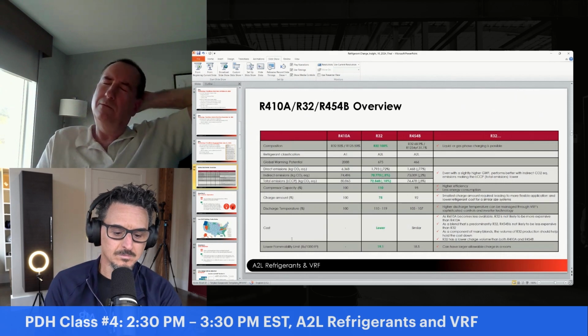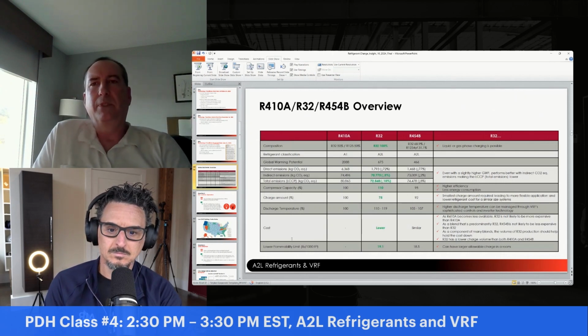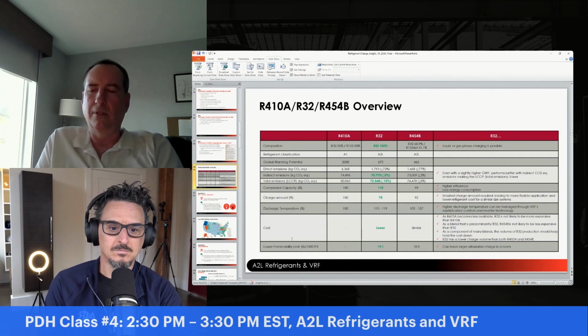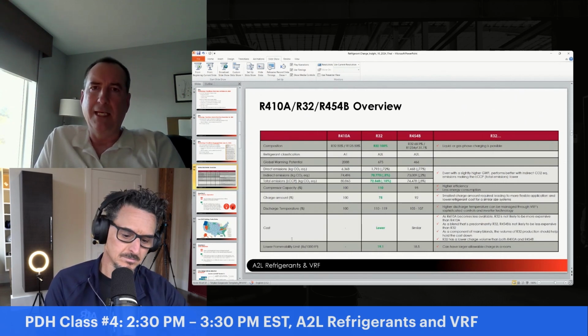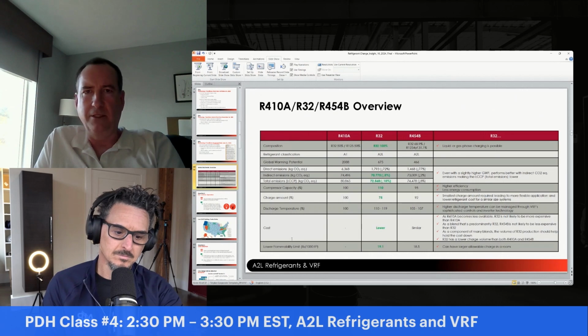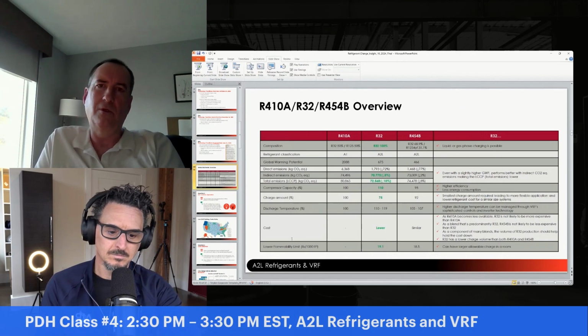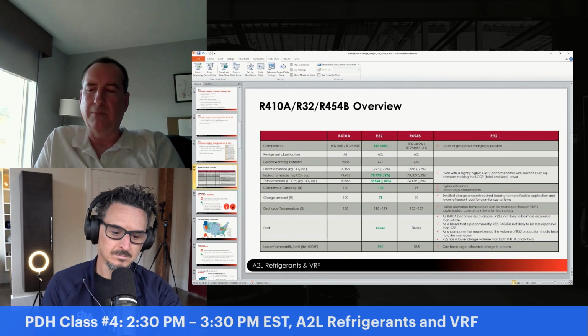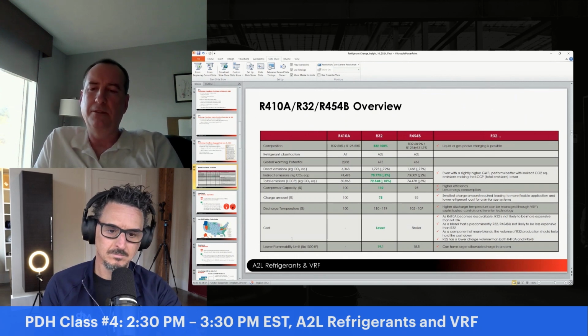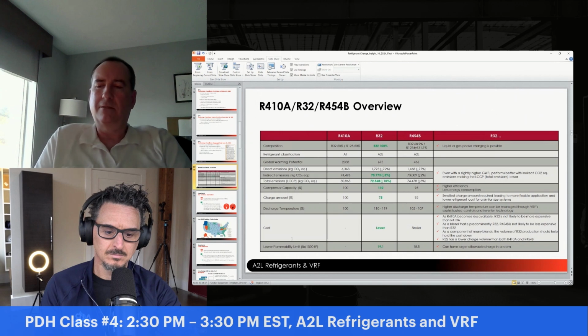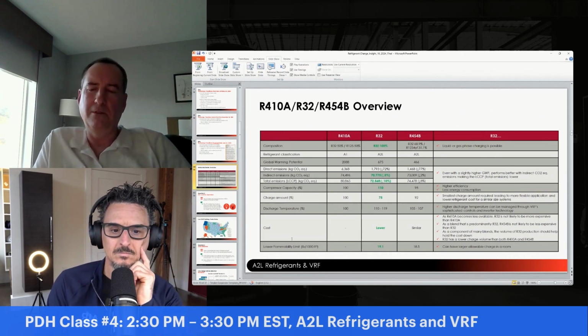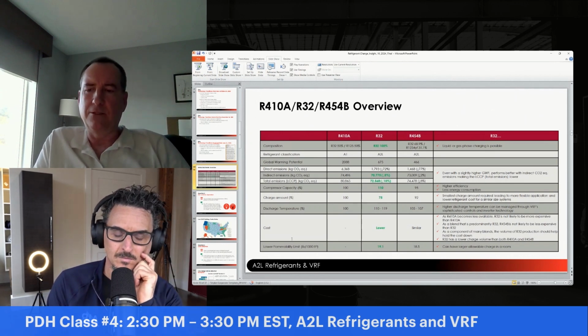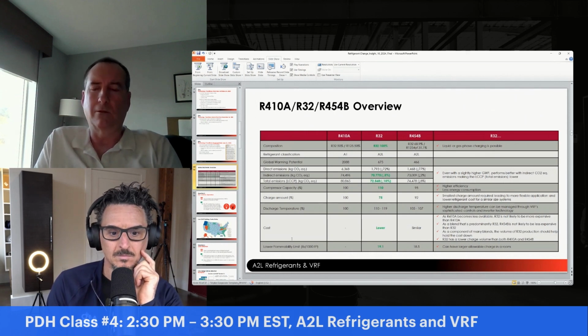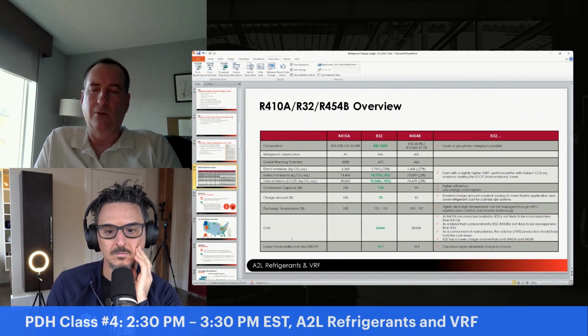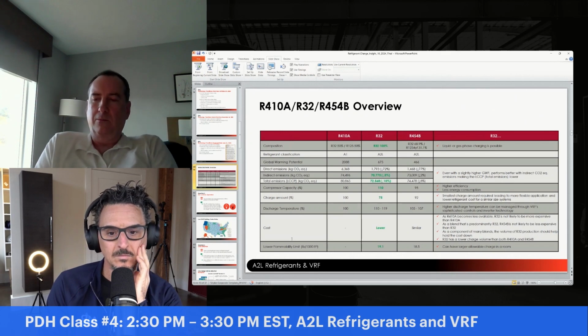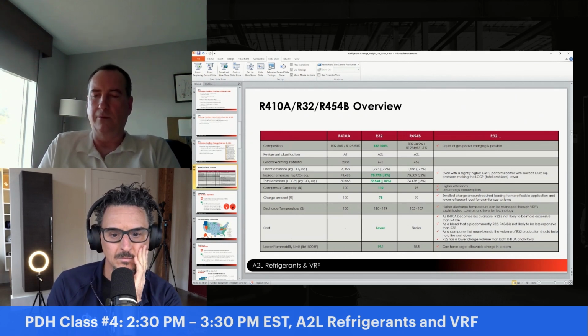Looking at these new A2L refrigerants, some people have chosen R32, some are going with 454B. This chart shows the different advantages of using one versus the other in different applications. We chose R32 for our systems because it provides the greatest benefit to those systems using that refrigerant. It's chlorine free and has a lower GWP fluorocarbon with an ODP of 0.